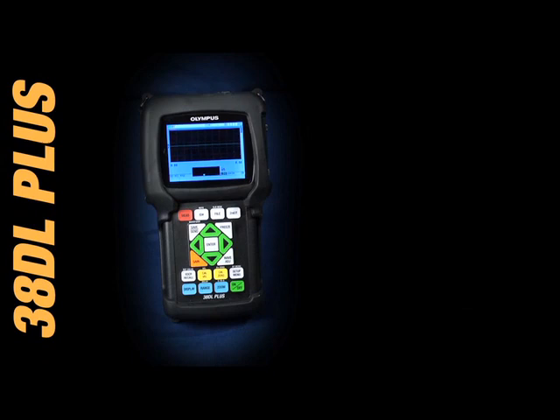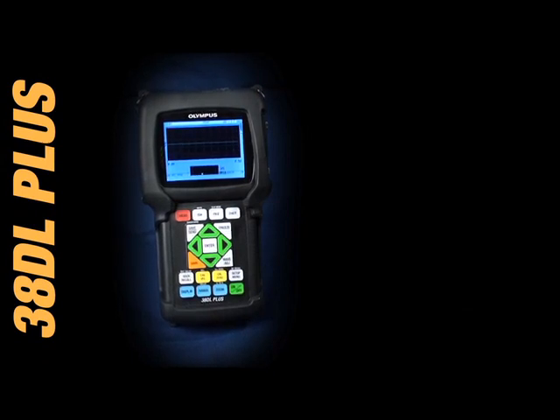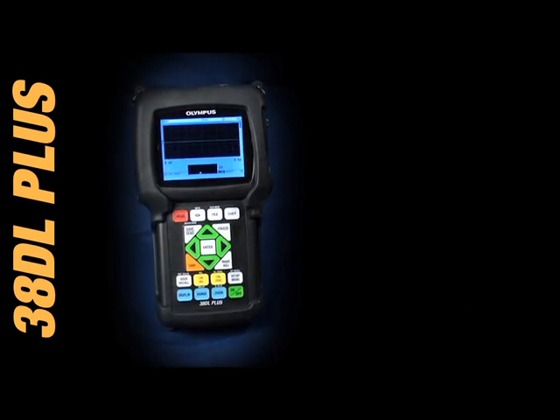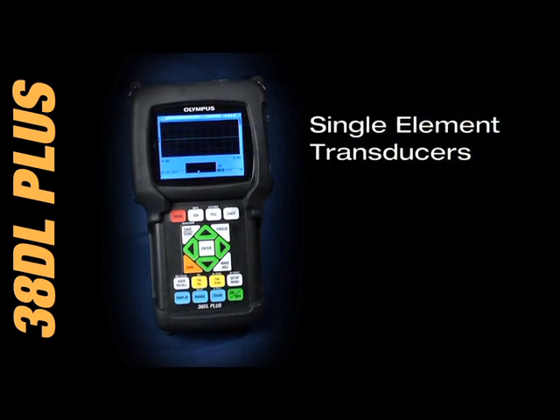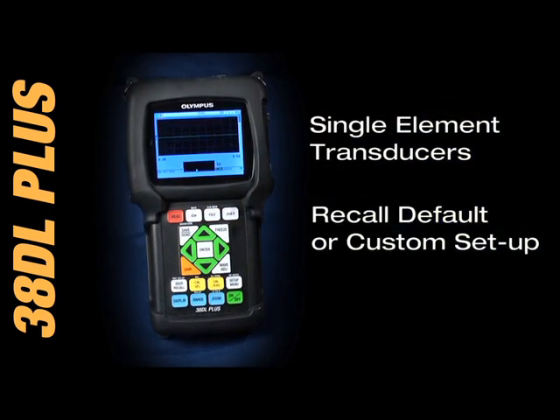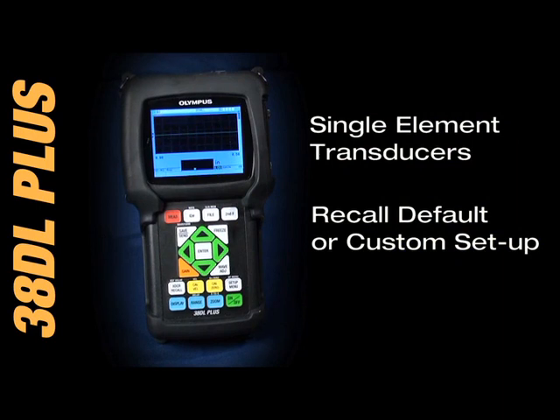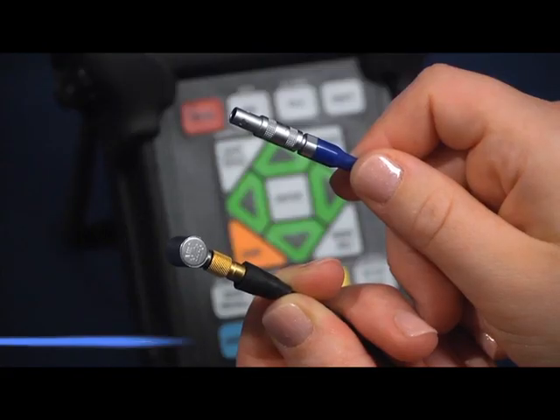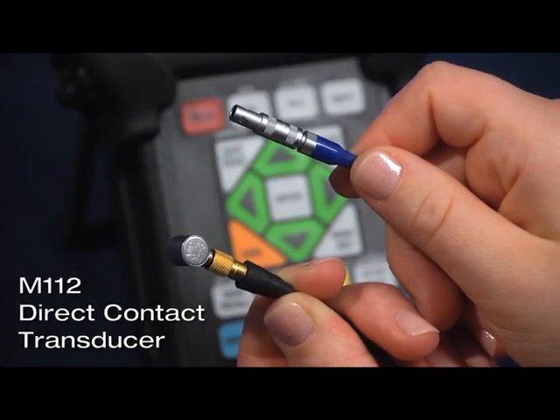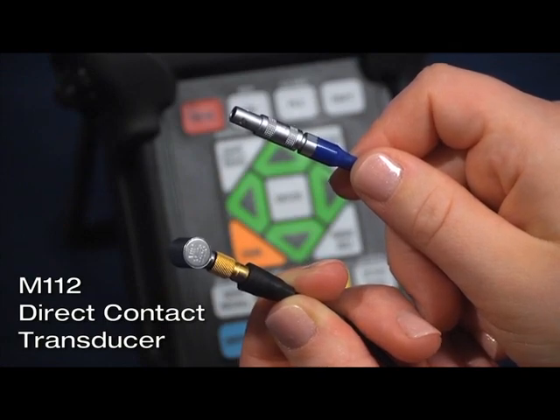Today we are going to discuss how to recall, calibrate, and store a single element transducer setup on the 38DLplus. The 38DLplus has the ability to use both dual and single element transducers. When using a single element transducer, it is necessary to recall a default setup or a custom setup for the transducer being used. In this example, we will be using a M112 direct contact transducer.